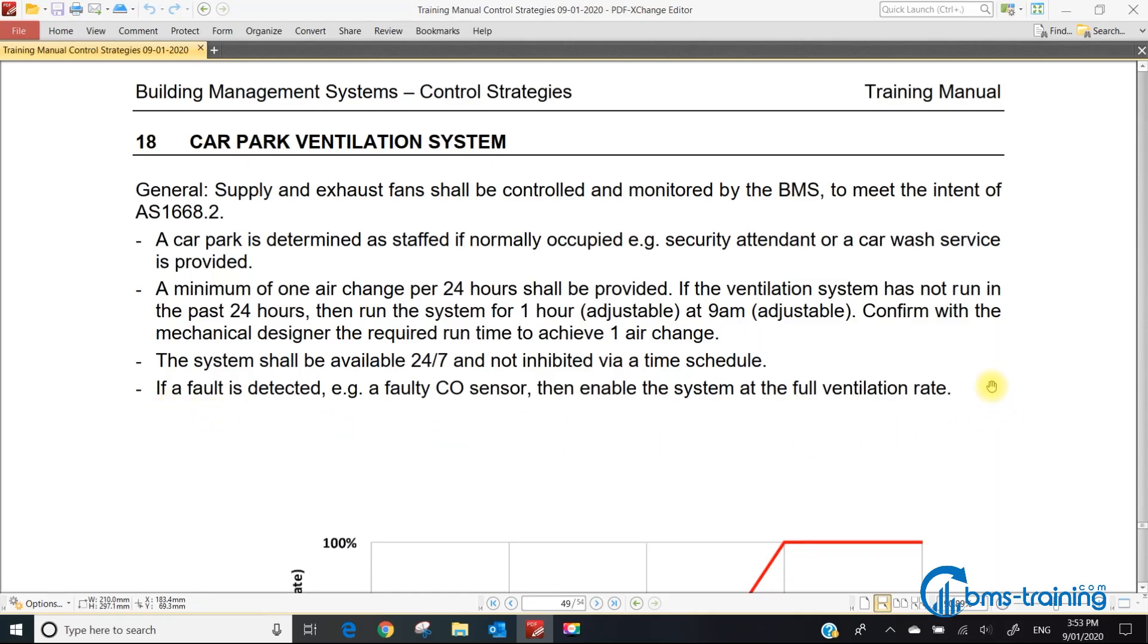If a fault is detected, for example a faulty CO sensor, enable the system at full ventilation rate. In the old days we had to run car park ventilation to design all the time. With the introduction of CO sensors, we're now permitted to run the fan lower than design. If something goes wrong and your CO monitoring is at fault, you've got to run it at full ventilation rate.